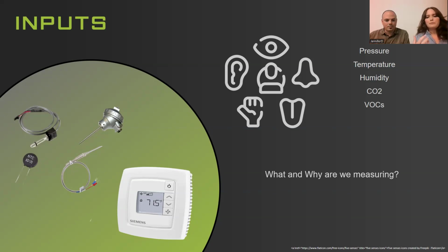An example of a sensor where size would be important is a temperature sensor within a duct. You wouldn't necessarily use a tiny little probe sensor in that space if you were putting it into giant ductwork, because it's just not going to be able to measure what's going on there.